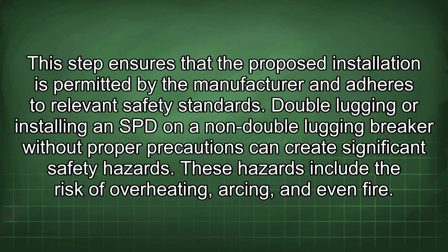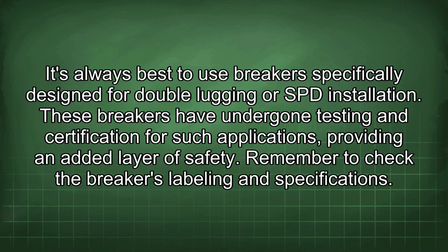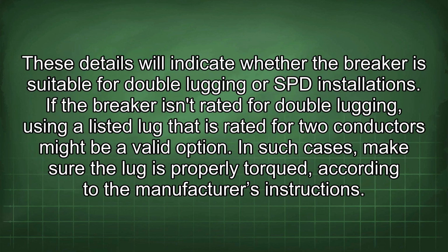Double lugging or installing an SPD on a non-double lugging breaker without proper precautions can create significant safety hazards. These hazards include the risk of overheating, arcing, and even fire. It's always best to use breakers specifically designed for double lugging or SPD installation. These breakers have undergone testing and certification for such applications, providing an added layer of safety. Remember to check the breaker's labeling and specifications. These details will indicate whether the breaker is suitable for double lugging or SPD installations.